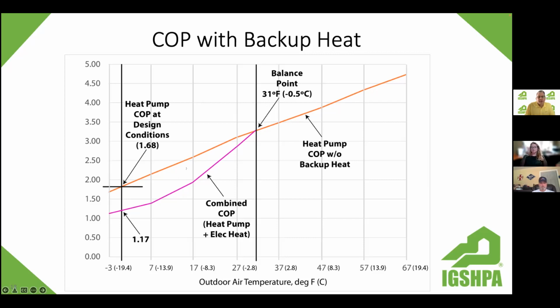So this line right here in red tells us what the efficiency of that heat pump is, and it's just the heat pump, does not include electric heat, from 67 degrees outside Fahrenheit down to about -3. And so when we look at this particular example, the 61,000 heat loss, we have our balance point at 31 degrees. This purple line is the combined COP. So this is the efficiency of the heat pump with electric heat. Once we get below 31 degrees, we have to start bringing on some degree of electric heat, all the way down to design conditions. Good news is that all the way down to 0 degrees, we still have an efficiency better than 1. So it's still better than having just electric heat running.